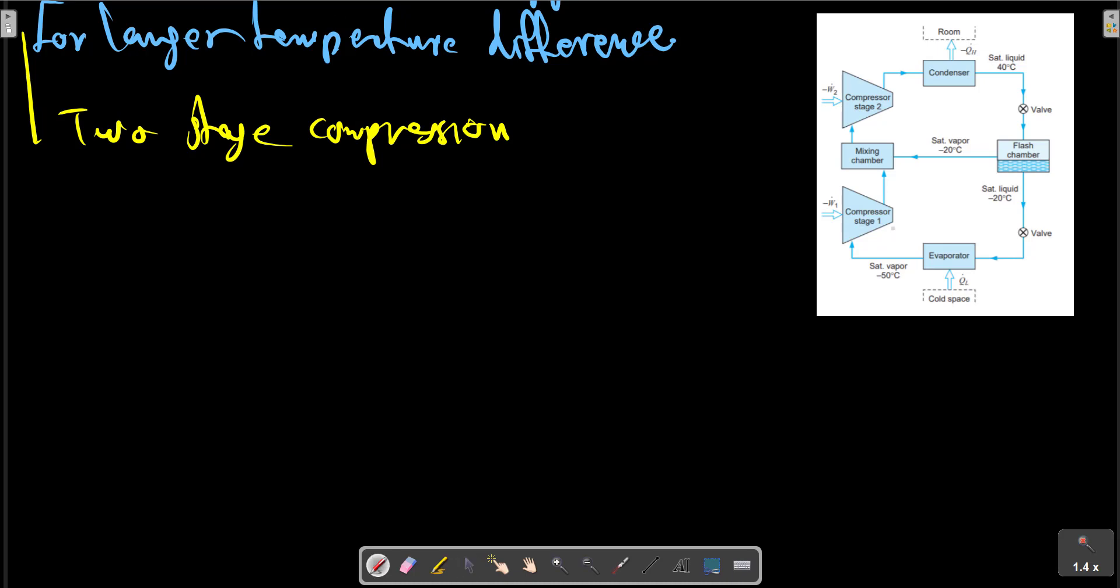So the two-stage compressor here has a flash chamber, and a mixing chamber. As there is no cooling medium with such a low temperature, the lowest temperature compressor then handles smaller flow rate at very large specific volume, which means larger specific work. The net result increases the COP.